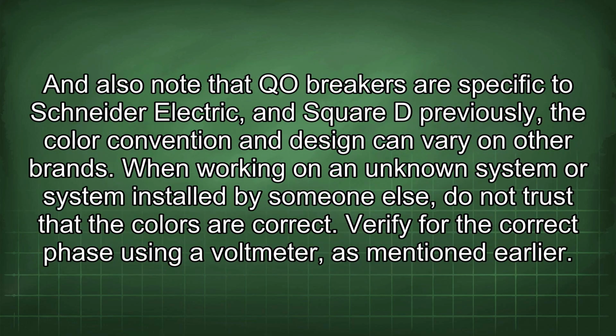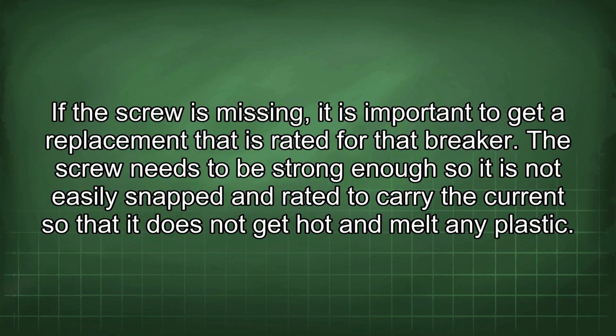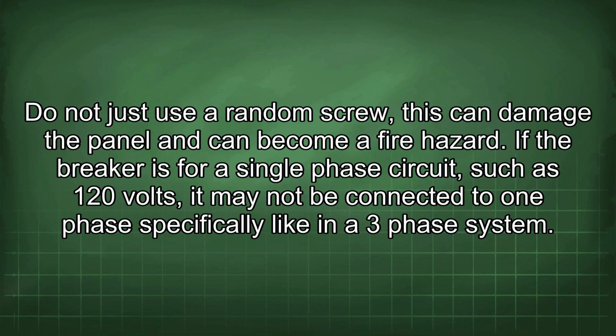And also note that QO breakers are specific to Schneider Electric and Square D previously. The color convention and design can vary on other brands. When working on an unknown system or system installed by someone else, do not trust that the colors are correct. Verify for the correct phase using a voltmeter, as mentioned earlier. If the screw is missing, it is important to get a replacement that is rated for that breaker. The screw needs to be strong enough so it is not easily snapped and rated to carry the current so that it does not get hot and melt any plastic. Do not just use a random screw, this can damage the panel and can become a fire hazard.